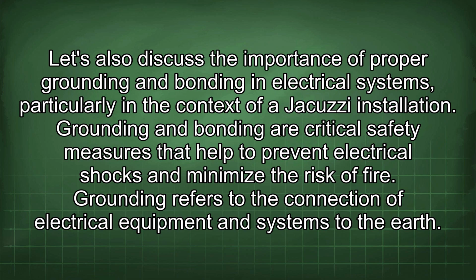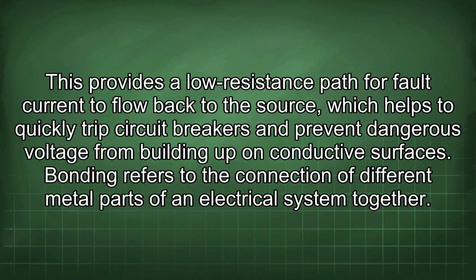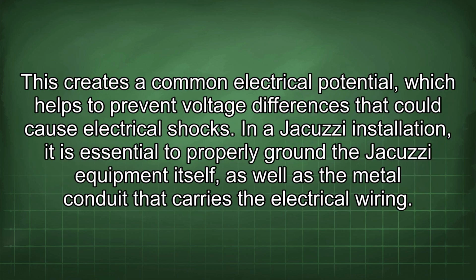Grounding refers to the connection of electrical equipment and systems to the earth. This provides a low-resistance path for fault current to flow back to the source, which helps to quickly trip circuit breakers and prevent dangerous voltage from building up on conductive surfaces. Bonding refers to the connection of different metal parts of an electrical system together. This creates a common electrical potential, which helps to prevent voltage differences that could cause electrical shocks.